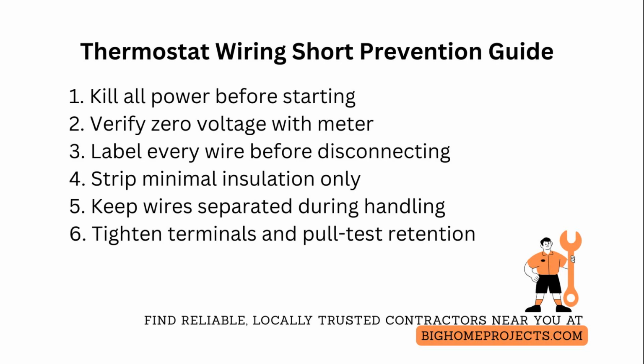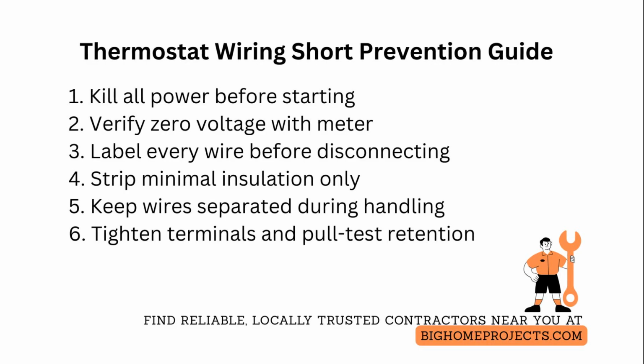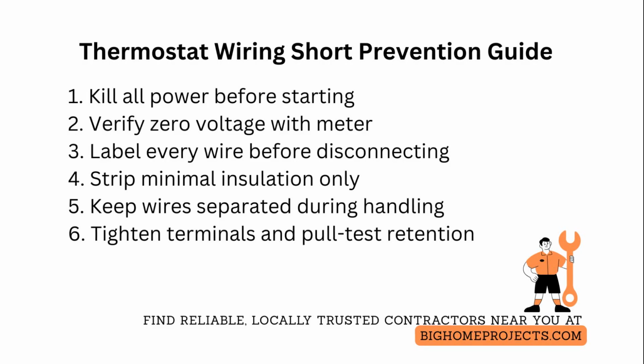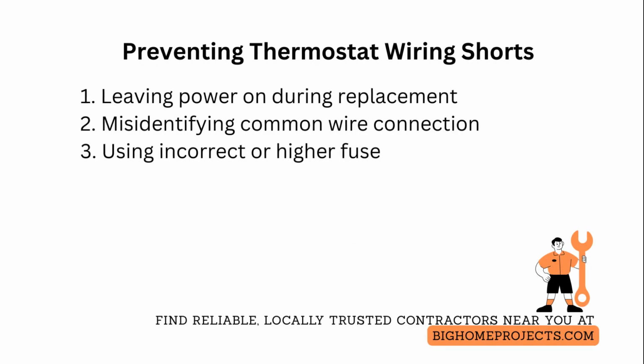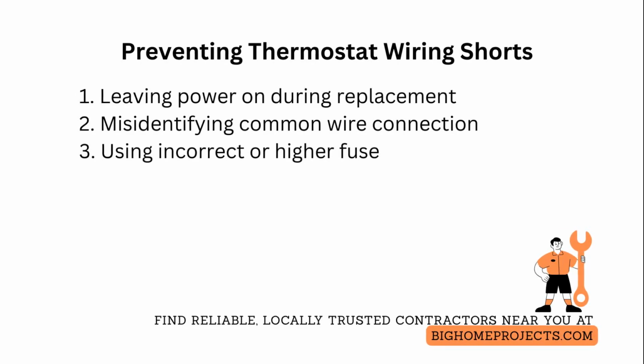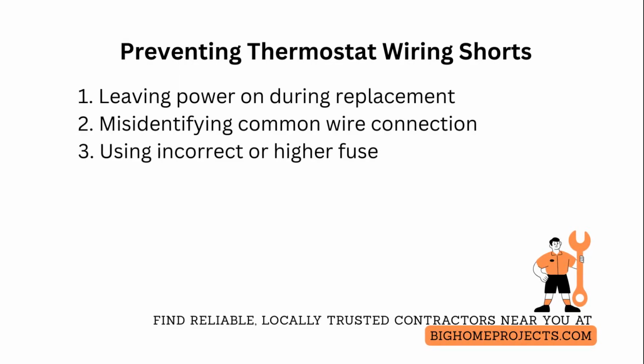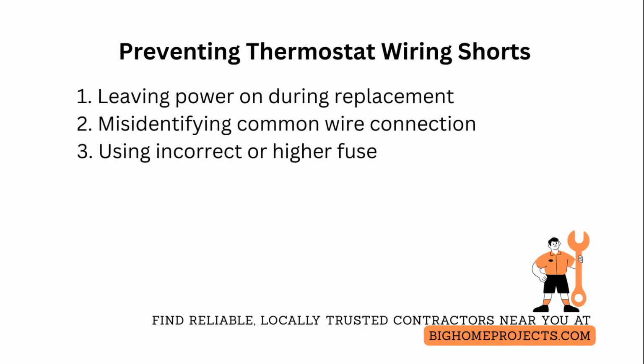Finish by securing wires with a strain relief and routing them so no conductor can contact the metal backplate or each other. Then power up and verify system operation through a full call for heat and cool sequence. One of the top 3 common mistakes is working with power still applied, which causes blown control fuses and system outages. Fix that by turning off the breaker and verifying 0 voltage before touching wires.